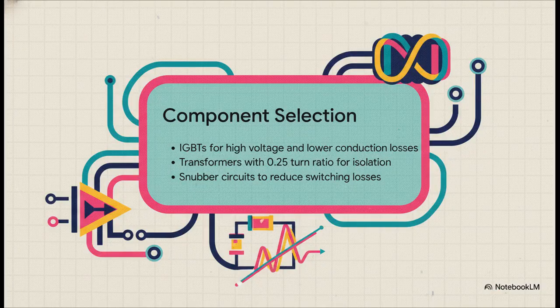And this brilliantly illustrates exactly what's under the hood, making that topology tick. First up, we're using IGBTs. Why? Because at 80 kilowatts, standard MOSFETs are going to struggle with conduction losses. IGBTs are chosen specifically for their high voltage handling and lower conduction losses at these massive power levels.